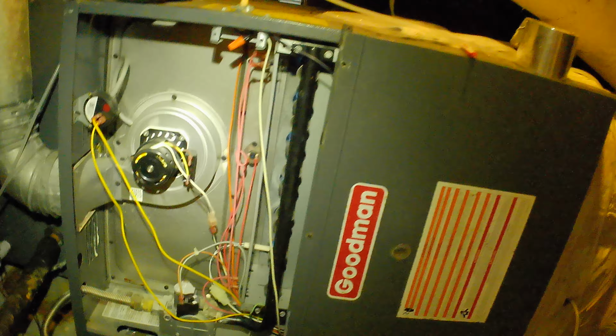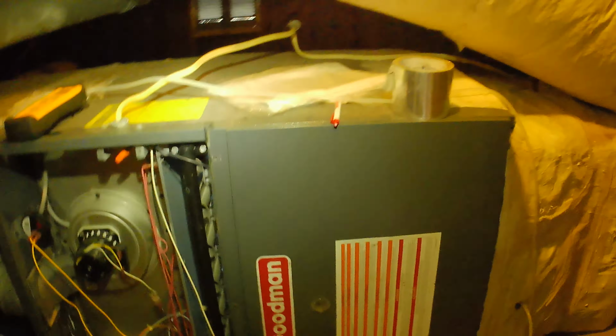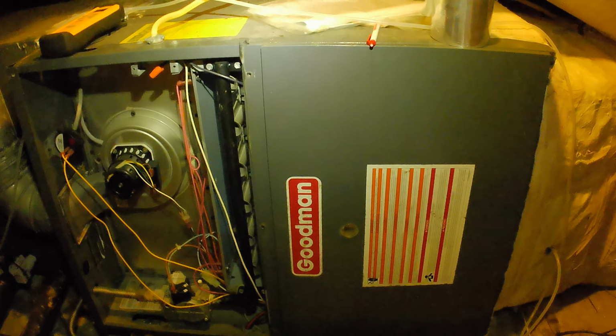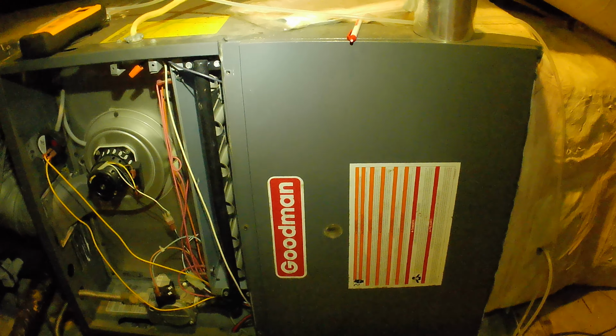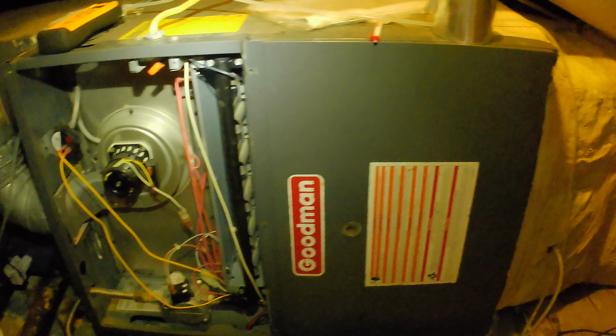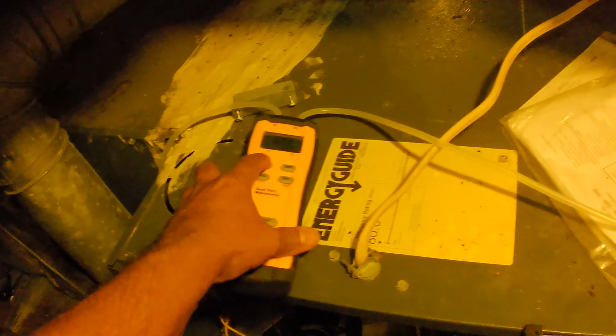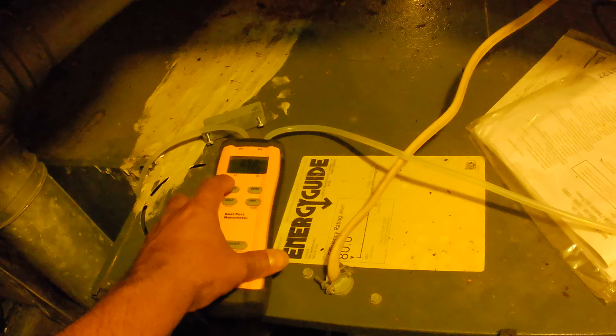Right. Hello. We're doing maintenance on this furnace today. I was checking the flame sensor, the microamps. We're supposed to clean it every season. Then we're gonna check static pressure. We're actually checking the static pressure right now, and it looks like we're a little bit higher.